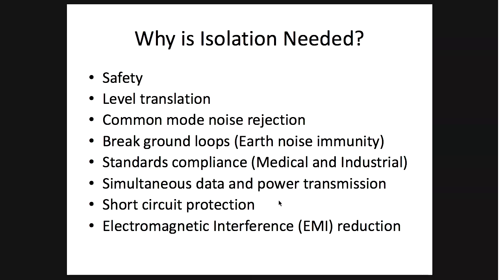If you are going to work in medical devices, there will be a lot of isolation, because you don't want the patient getting a shock. Why I am teaching isolation is because I don't want to die when I go to hospital because of some pain in my muscle. If you design equipment without isolation, then I will die of electric shock. I don't want that to happen.